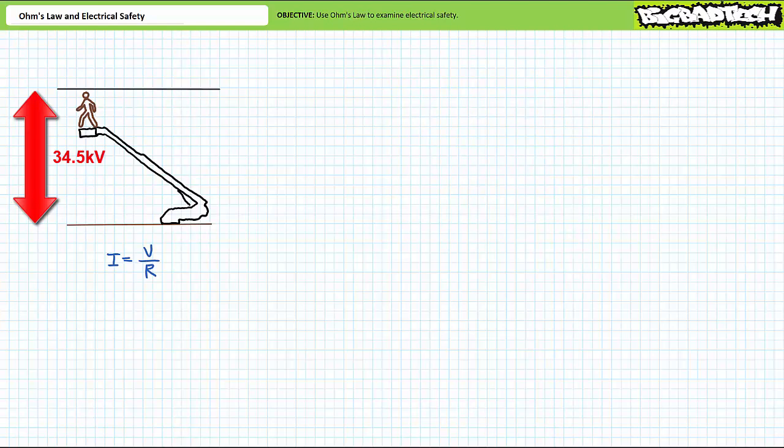First, everything is a conductor. However, some conductors are better than others. A saltwater-soaked person is an especially good conductor with low resistance. Second, a metal platform is also a low-resistance conductive path connected to Earth, something we often use as a reference for voltage measurements. Third, the wire is high voltage. The magnitude of this voltage is often made with reference to ground, that same plane the worker is connected to via the metal platform. If the worker touches the wire, there is a high-voltage differential across a low-resistance path, and substantial current will flow.